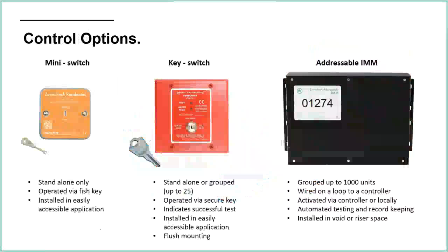The residential zone checks can be controlled in three different methods. We have the mini switch option, which is the cheapest option. All that does is run the pump. So it's like a manual switch: turn it on, turn the pump on, turn it off. You'd need somebody to make sure that the signal is actually getting through with that one.